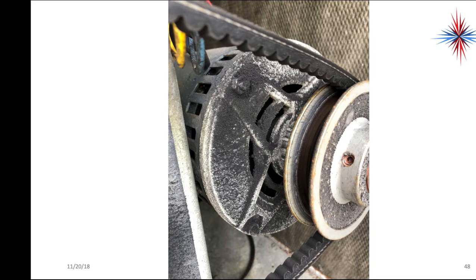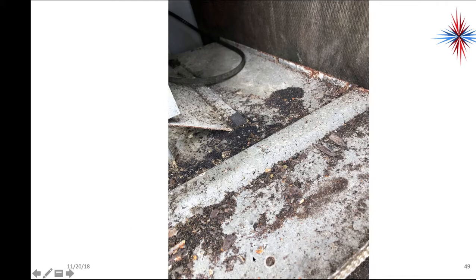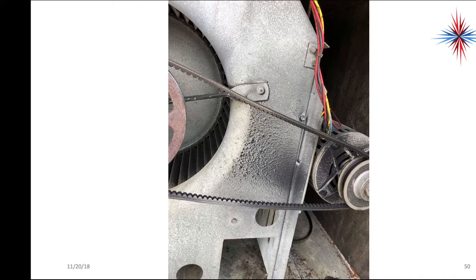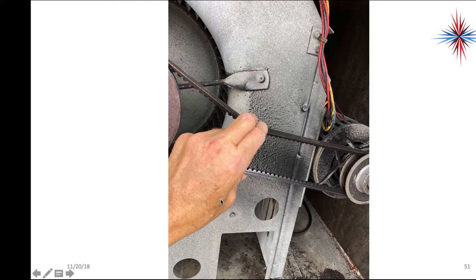Took a closer look, and I found a belt that was starting to go bad. There's, believe it or not, another bad belt laying in the air handler. I see a lot of debris around, lots of rust. Notice the sag in this belt here. This belt is very, very loose on here. It's really not at the correct tension at all. You should be able to push in half an inch on a belt for tension. This belt is really, really loose. It's probably not driving much of anything. It's probably sitting here spinning and smoking.